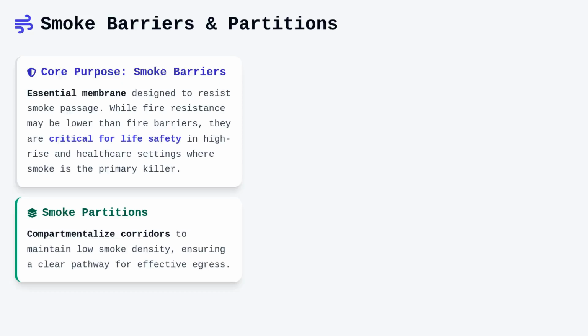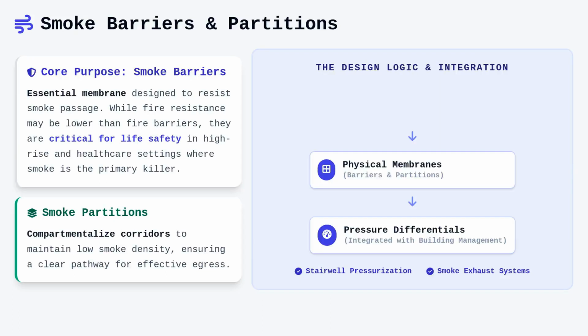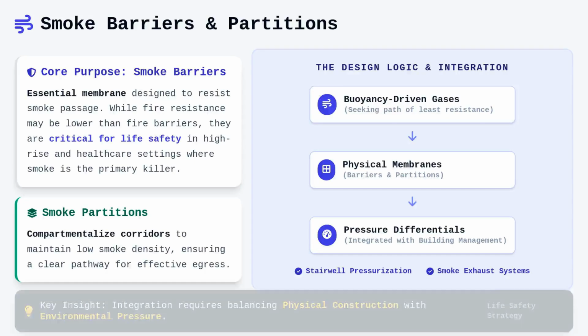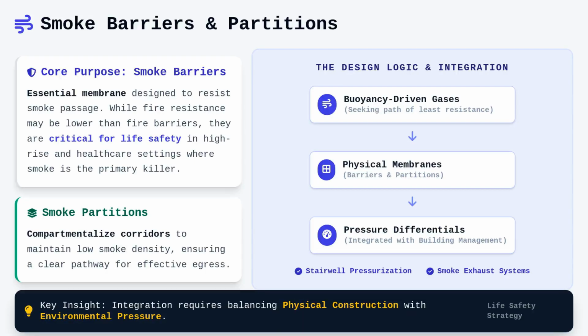egress. We rely on these membranes to create pressure differentials, working in tandem with building management systems, such as stairwell pressurization or smoke exhaust, to maintain a clear egress pathway. The design logic here is predicated on controlling the movement of buoyancy-driven gases, which tend to seek the path of least resistance through every crack or doorway. Understanding how to integrate these barriers requires a deep appreciation for the interaction between physical construction and environmental pressure.